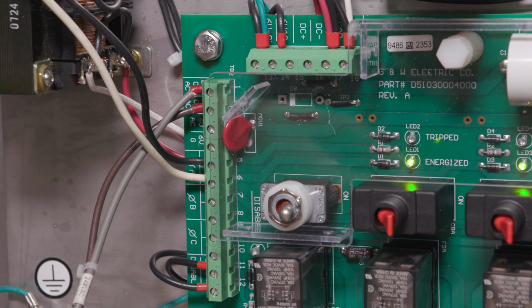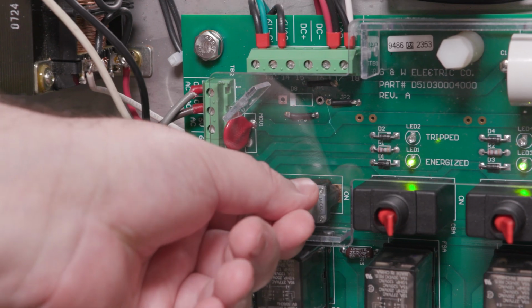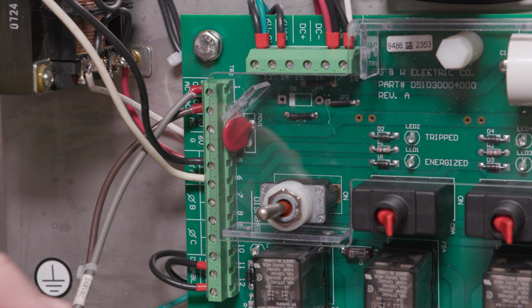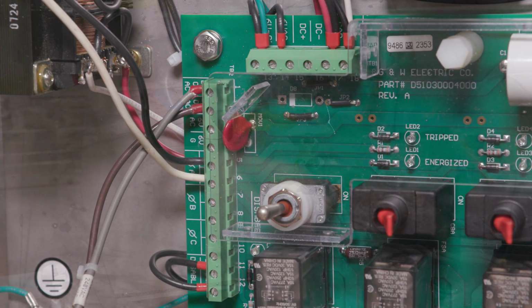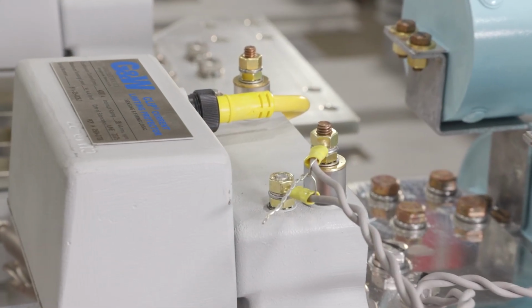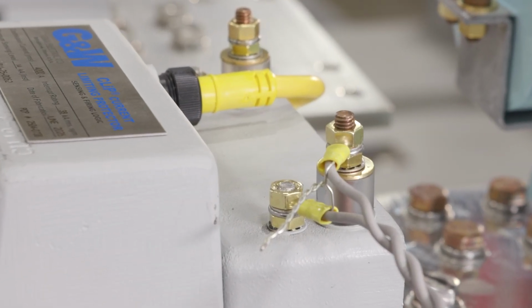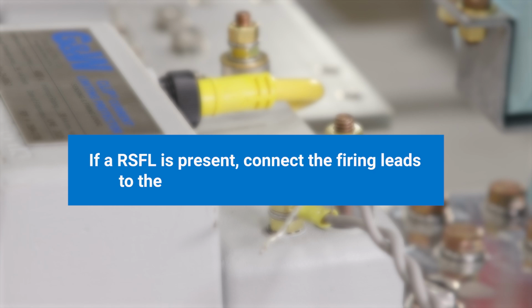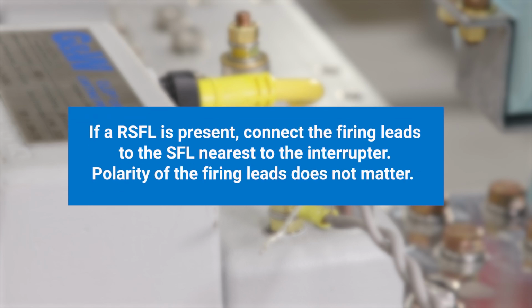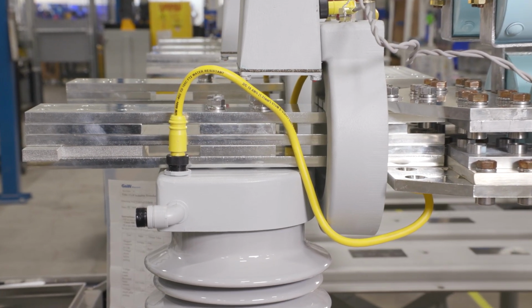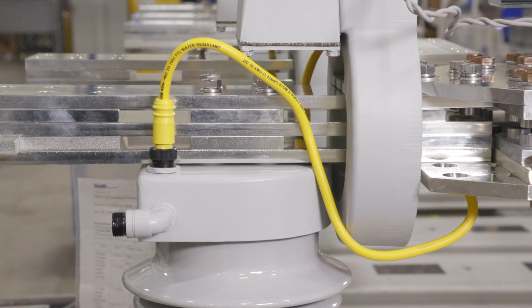Verify that the power is connected to the control box. De-energize the CLiP current limiting protector's electronics. Attach the firing leads to the SFL while the firing leads are shorted. If an RSFL is present, then connect the firing leads to the SFL nearest to the interrupter. Polarity of the firing leads does not matter. Now verify that the yellow cables between the IT and the SFLs are connected and fully seated. Then remove the bare shorting wire from the firing leads.